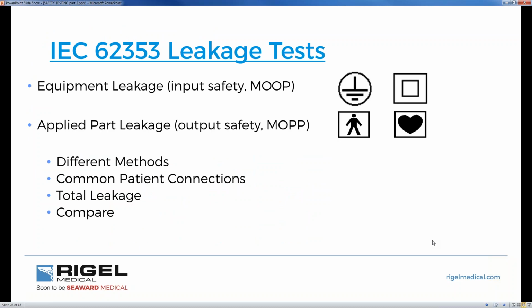So 62353 leakage tests. We have equipment leakage, which is input safety, means of operator protection. And then we have applied part leakage, output safety, which is means of patient protection. We use different methods of leakage tests, and I'll go through each one of those individually. We common patient connections, so slightly different to 60601. We're measuring the total leakage of the system. And we're also comparing and analysing results.